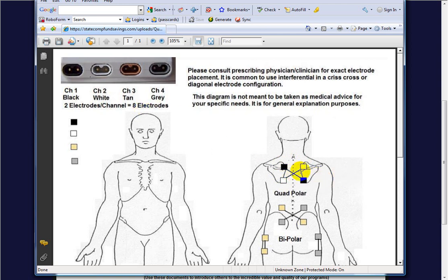Because one channel is going in at 4,000 Hz and the other at 4,000-plus, the signal achieves deep penetration through the skin and body tissue. Instead of going in at 0 to 150 Hz, it's going in at 4,000 to 4,150 Hz. It penetrates with minimal impedance, and most people who use Interferential feel it is just more gentle.